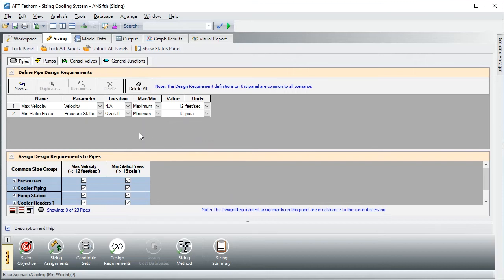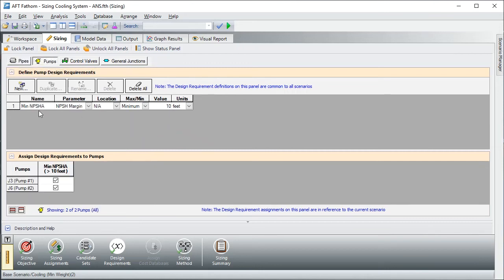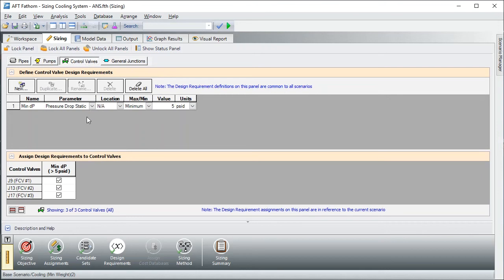For this system, we need a maximum velocity of 12 feet per second, so everything's got to be below that. We also have a minimum pressure, a minimum net positive suction head margin in the pump because we want to avoid cavitation, and in the control valve a minimum pressure drop that we're trying to control.